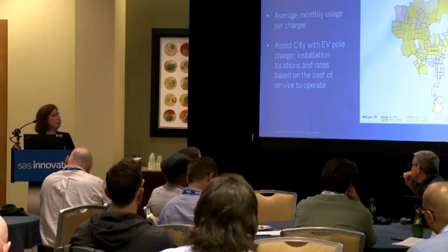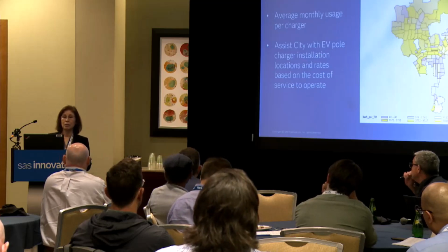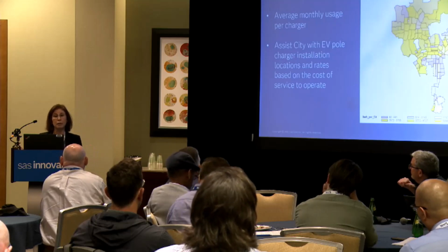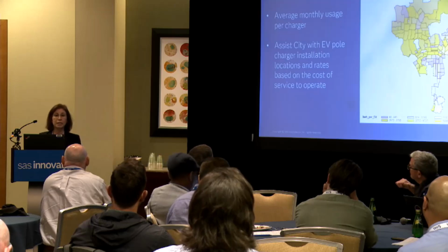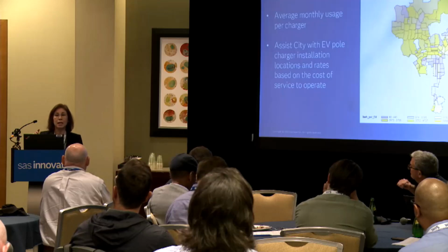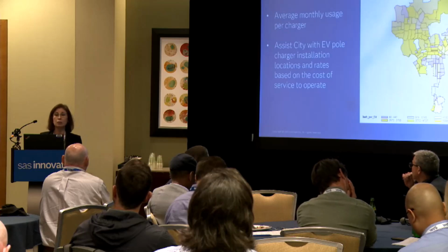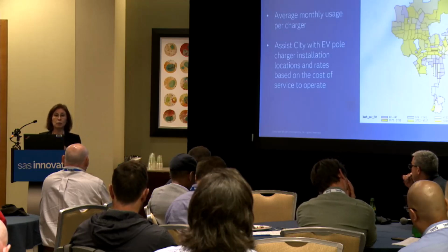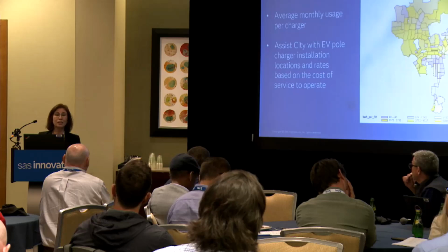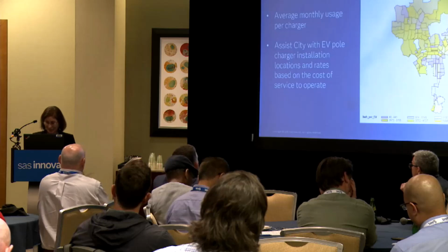And another key point about these single EV chargers is that our billing system could not handle the data of how much these chargers were being used because we do not have an electric meter on them. So we're relying on third-party data of when the chargers were plugged in, when they were unplugged, and how much consumption was used. And so we had to take that information and put it into SAS to actually calculate the amount of kilowatt hours used so that we could push it to our billing system in order to bill the other city department.